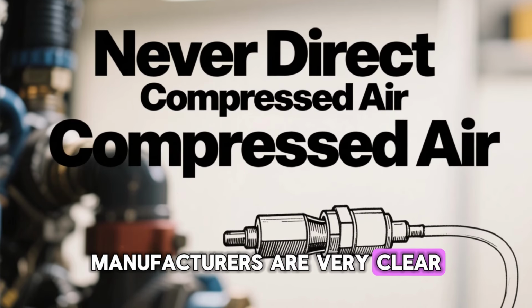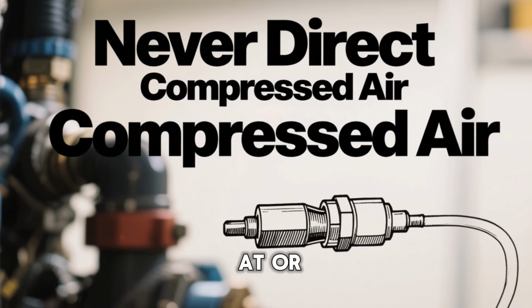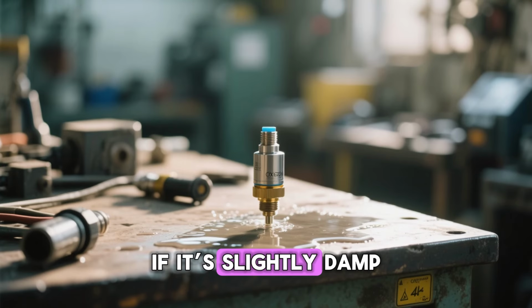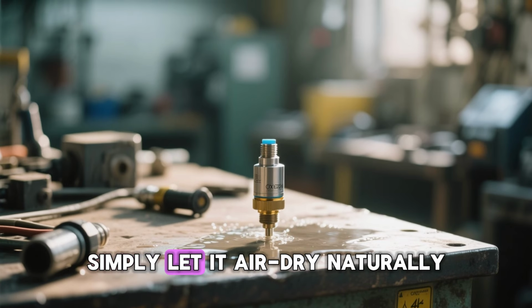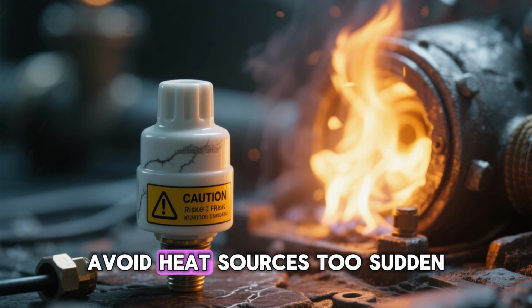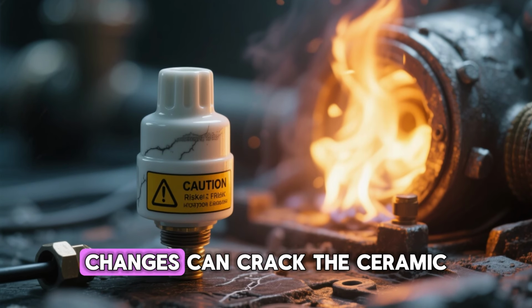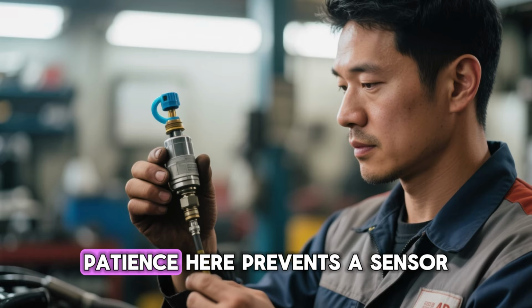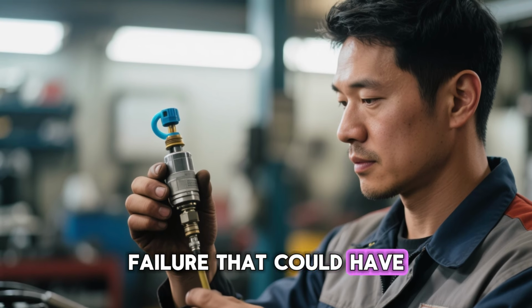Manufacturers are very clear: never direct compressed air at or through the sensor. If it's slightly damp from nearby cleaning, simply let it air dry naturally. Avoid heat sources too. Sudden temperature changes can crack the ceramic. Patience here prevents a sensor failure that could have been avoided.